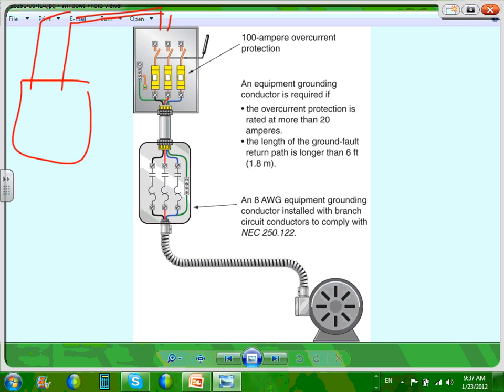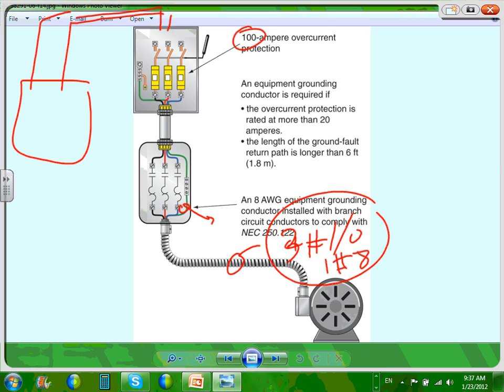I want to remind you of one little thing here. Can you guys see the equipment ground conductor? 3-phase conductors. So inside this conduit, there will be 4 conductors, whatever the size is. Based on this one, there will be different numbers because it's 100 amp. So let's just say 3 conductors, number 1 hot, and 1 conductor, number 8, inside that conduit. Any question about flexible metallic conduit? If it's outdoor, the only difference would be liquid tight flexible metallic conduit. Done.